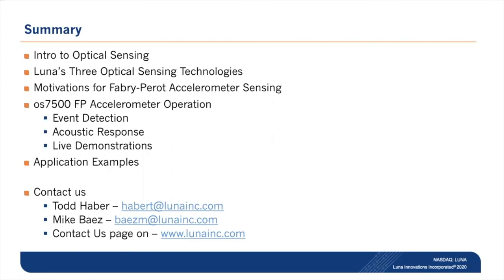What is the lowest range of frequencies these accelerometers can detect? Because these have some temperature sensitivity, they aren't appropriate for absolute or DC measurements. However, in collaboration with NIST we've shown good 0.1 Hz response. The data we took capturing the California earthquake had periods on the order of 10 seconds. We're confident in a linear response down to almost DC.